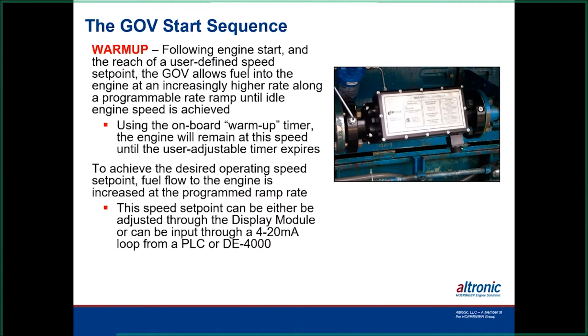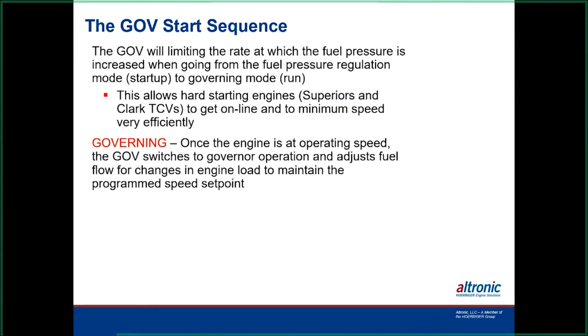Then you can dump in the RPM you're looking for and get it up to speed. The governor will limit the rate at which the fuel pressure is increased when going from the fuel pressure regulator mode at the startup into the governor mode. So that's sort of the unique thing about the valve. It's one valve, but it does two different things and has two different setup patterns when you program it.